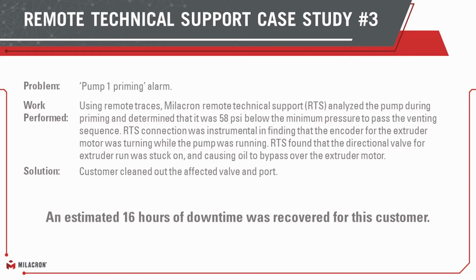So the first one here happened to be a pump one priming issue. So pump one priming alarm, meaning that when our machine is trying to check the state of the pumps and the health of the pumps, we do this at startup and we ask it to reach a certain pressure. If it does not reach a certain pressure within a certain time, our machine gives an alarm and says that there's likely an issue with this pump and we need to check it.